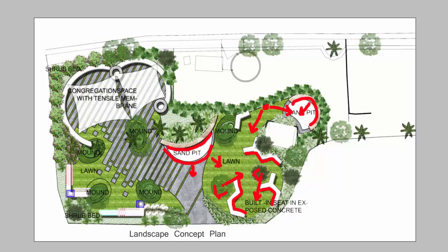And then for this mound, I'll just keep it like that. Either the kids will want to play on that area, but maybe the spill light coming from the pole light will be enough. Or if not, then there will also be spill light coming from the sand pit.